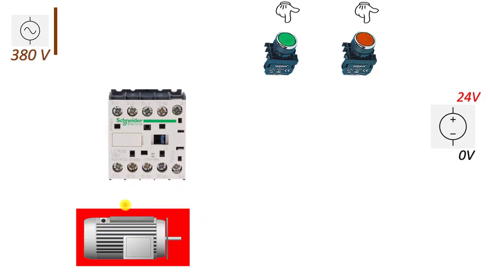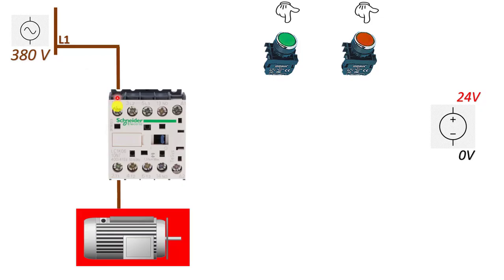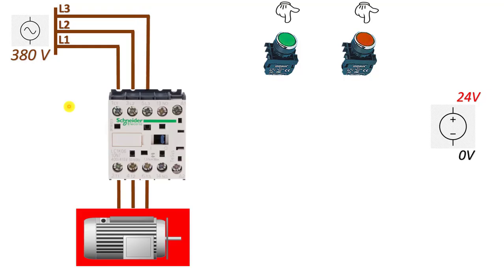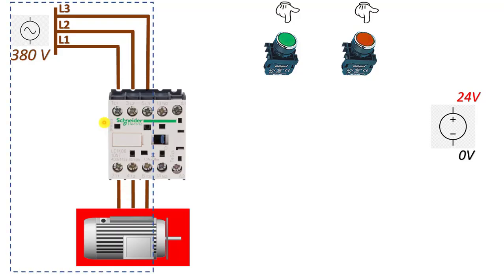The load we want to control is a three-phase asynchronous motor. I connect three phases of mains voltage to the three main contacts of the contactor. I take the L1 phase and enter the first L1 leg of the contactor, then get the output and connect the motor. Then I connect L2 to the second main contact, and L3 to the third contact. This way, all three phases are connected to the input of the three main contacts and the output goes to the three-phase motor — this is my power circuit.